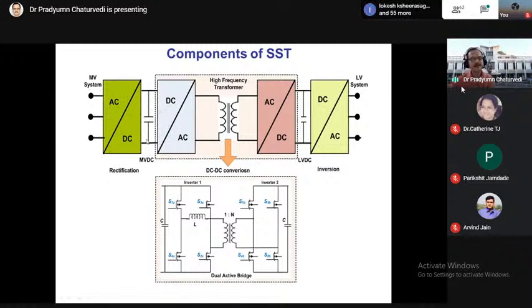Now this DC link is at one voltage level, like MVDC, around 10,000 volt DC. Invert this, use one HFT, again rectify this, use second DC bus here at LVDC bus rating, and if required then invert this to AC, otherwise stop at LVDC.